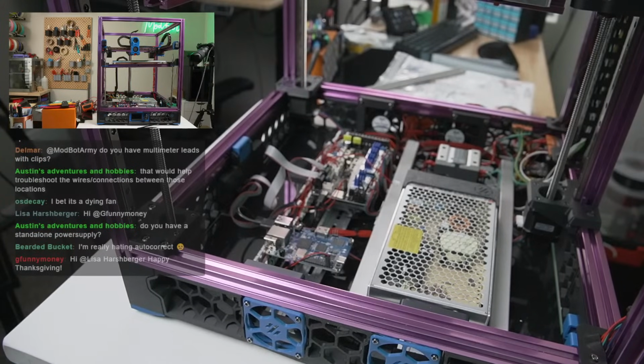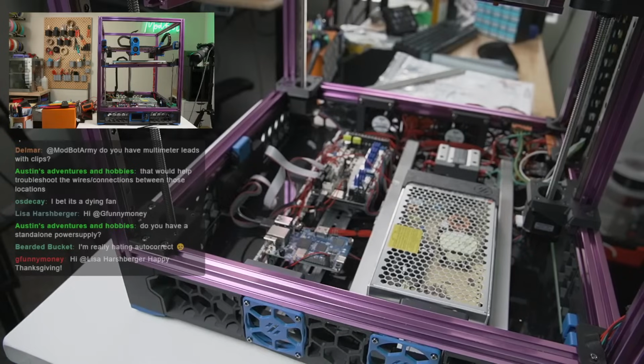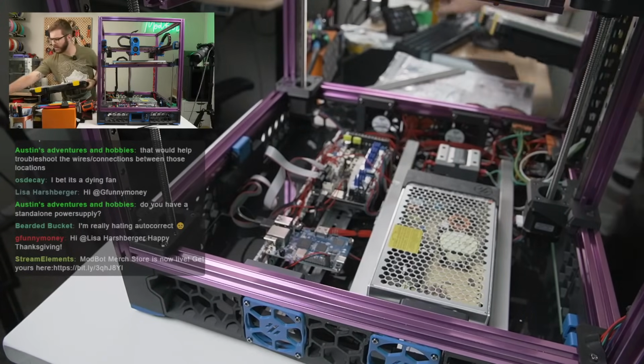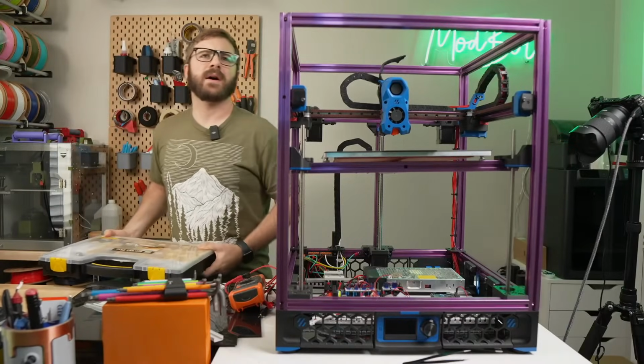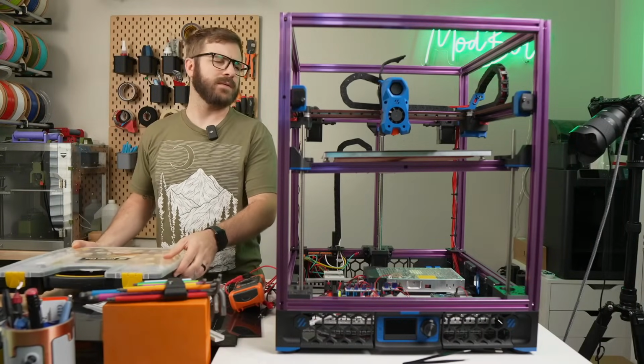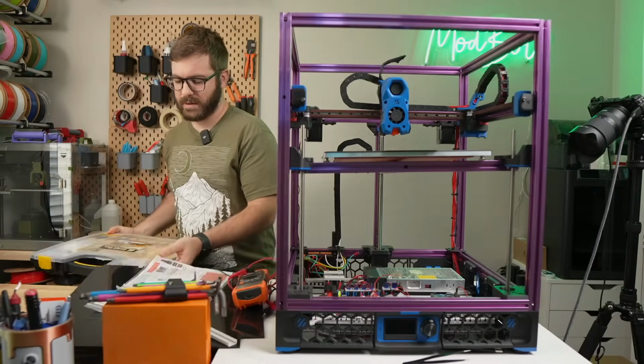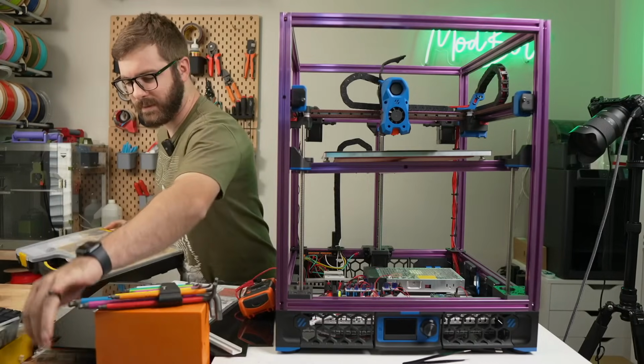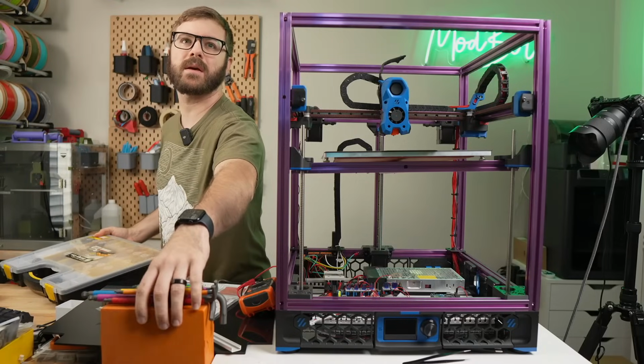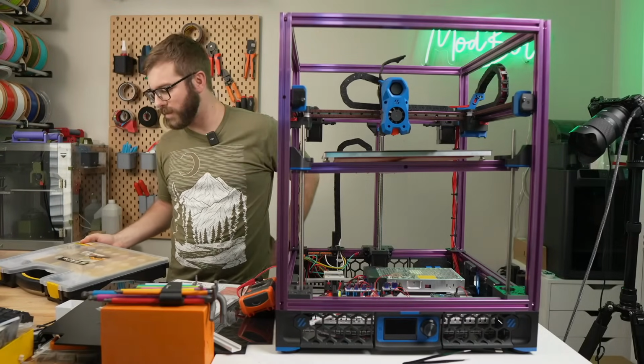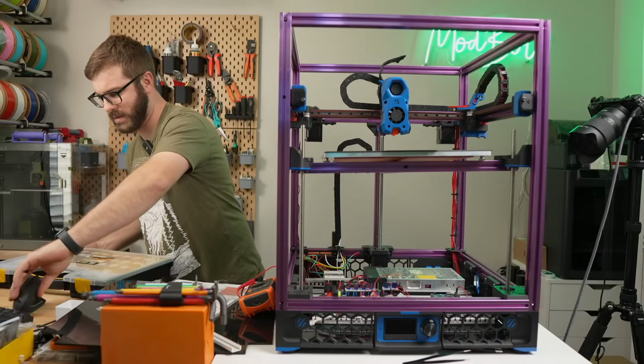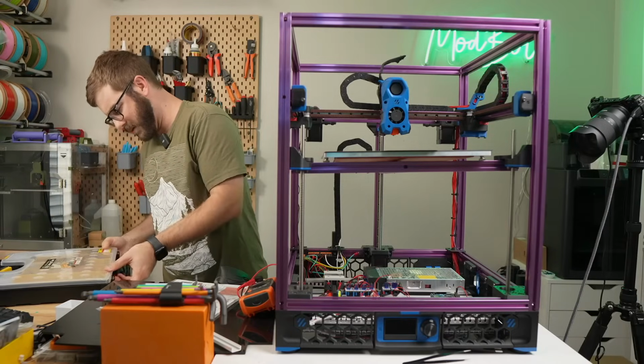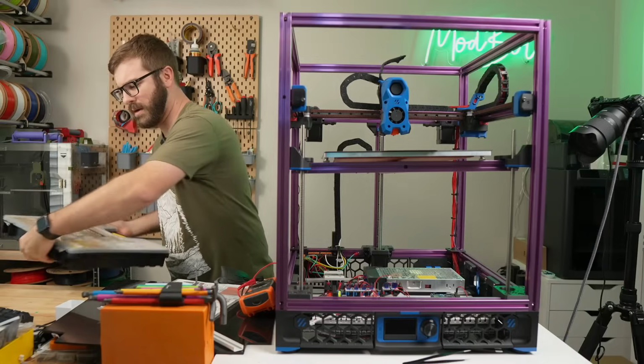If I grab, what size fan is it? Do we know? Let's just grab another 24 volt fan and rule out that the fan itself isn't the issue. I'm sure I've got an extra fan or two somewhere here. Just run a 24 volt wire from the spider board directly to your fan. Yeah, I would probably, oops, shit, drop stuff. I would probably, oh that's right, it's a 50-15 that's been cut up. Still think I've got one somewhere.